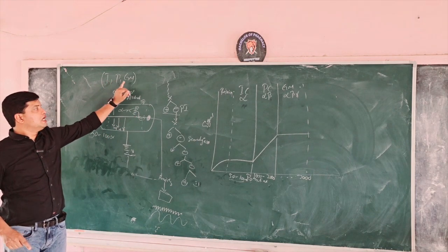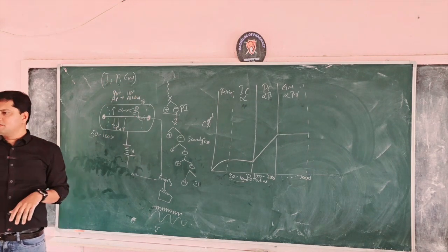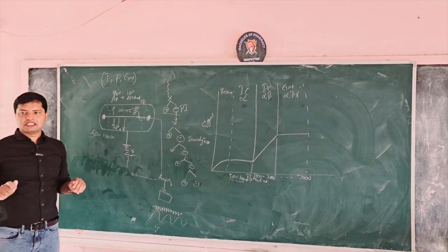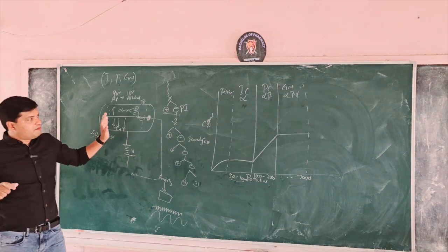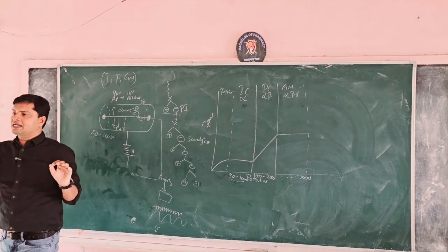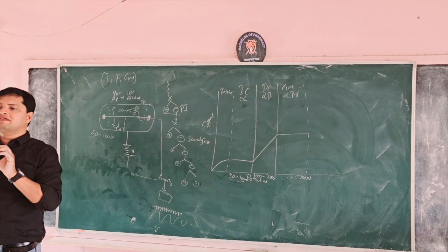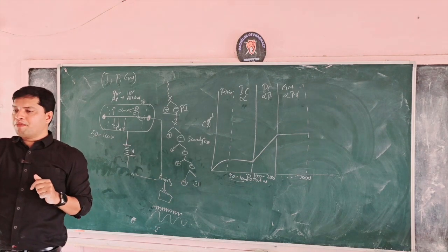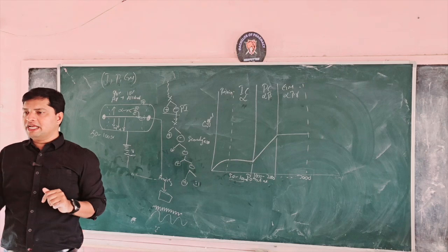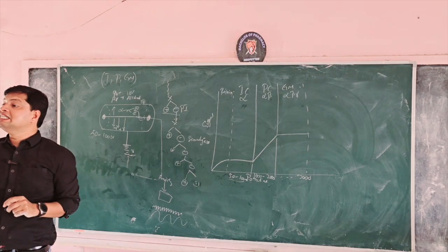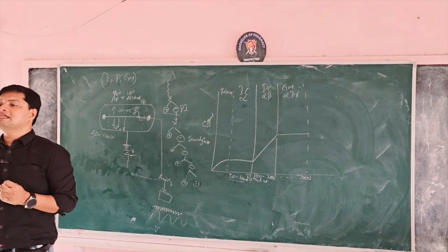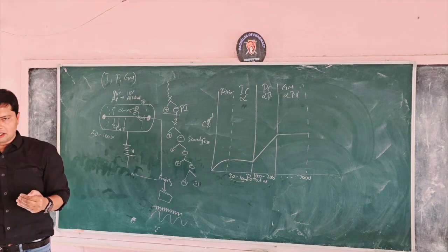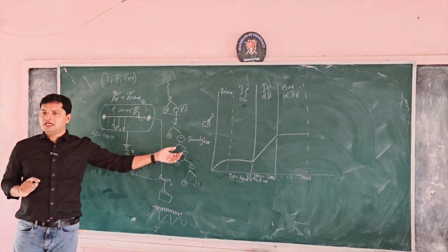Ionization, proportional and Geiger-Müller are all the same instrument; the only difference is the application of voltage. The basics: when radiation interacts with a gas molecule, it ionizes the gas molecule. In the process of ionization, it produces a positive ion and an electron. If I can measure the amount of electrons, I can directly say this is the strength of the radiation.